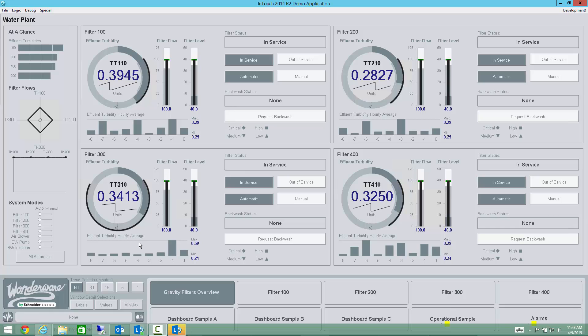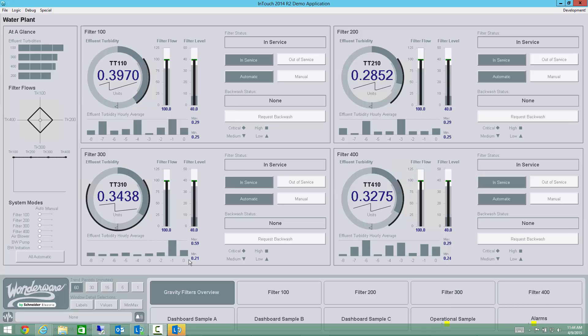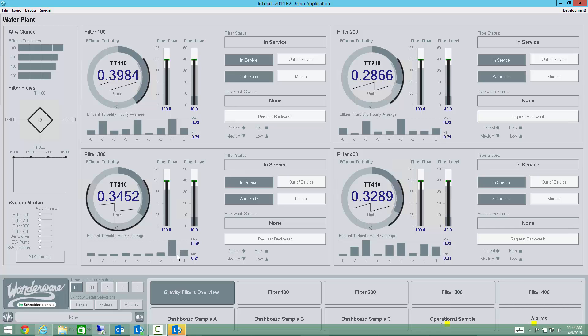If I look below these gauge type symbols here and look at these symbols labeled as effluent turbidity hourly average, what this allows me to do is to look at over the last eight hours. So this is the current hour labeled as zero, then hour minus one, minus two, minus three, back going kind of eight hours into the past. I can see what the hourly average is for this unit. I can see that its total span was from 0.21 to 0.59, and 0.59 is well outside of my expected range there. I can see that 0.59 occurred last hour. So my last hour was pretty bad, even though in this hour I'm much better. But I can see this information on an hourly basis.